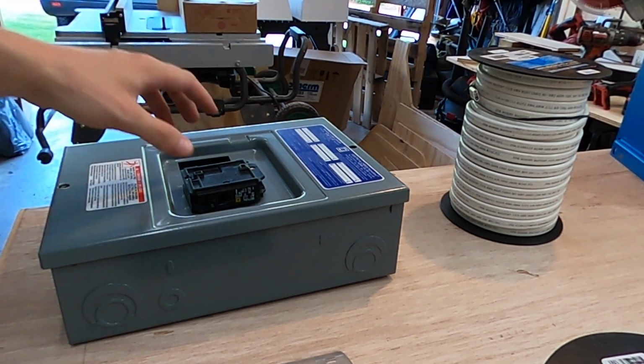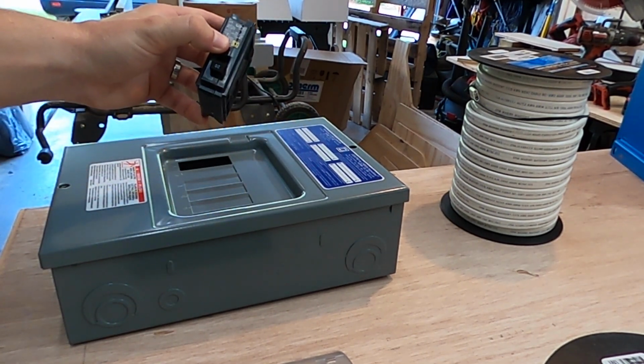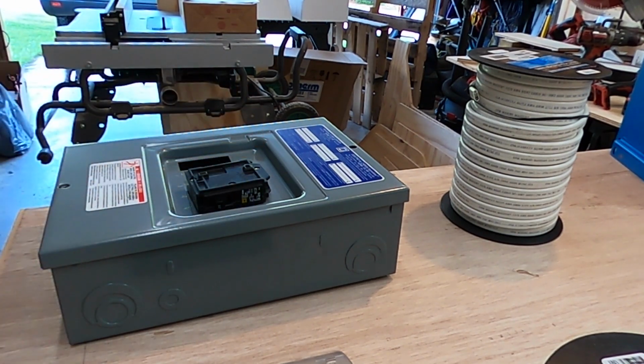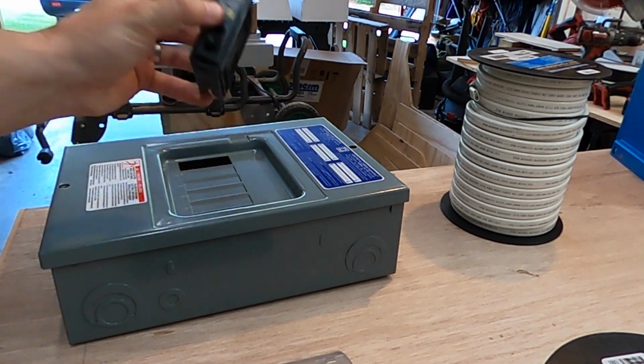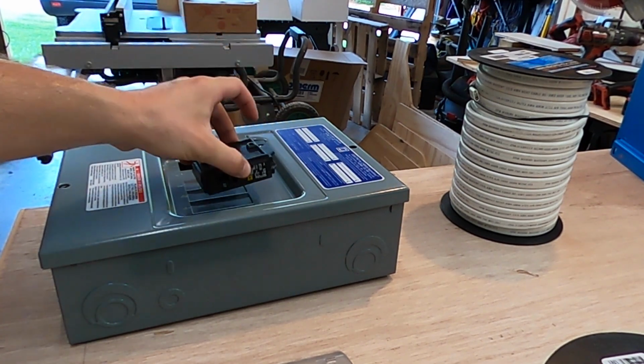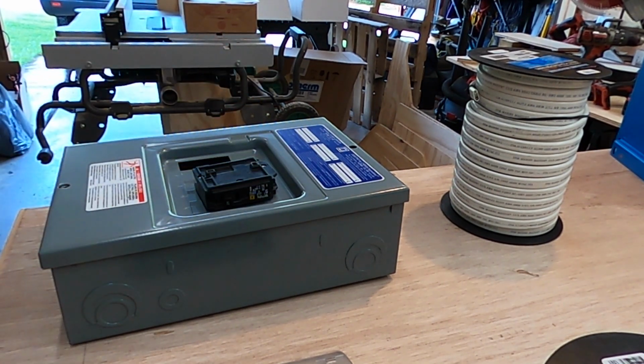Now the protection is the circuit breaker, so we've got a circuit breaker for every circuit we're going to run. Second to that, the circuits that will be near water will have GFI outlets on them. There's 2 ways you can do that: you can either run a GFI circuit breaker to protect the entire circuit, or put the GFI outlets where you know there's going to be water.